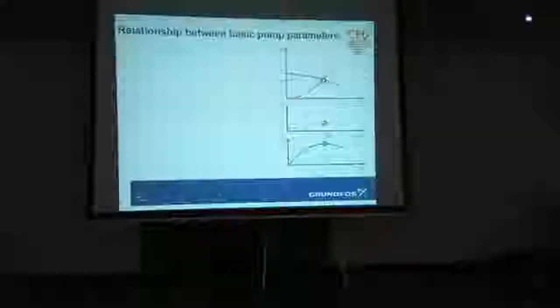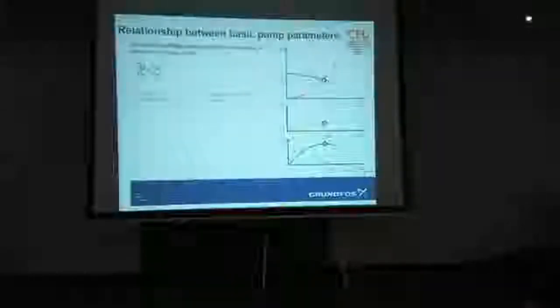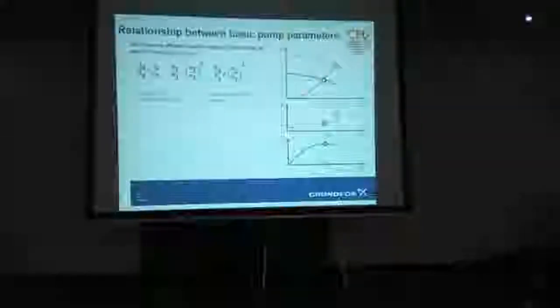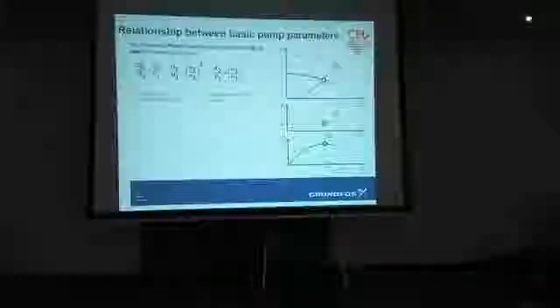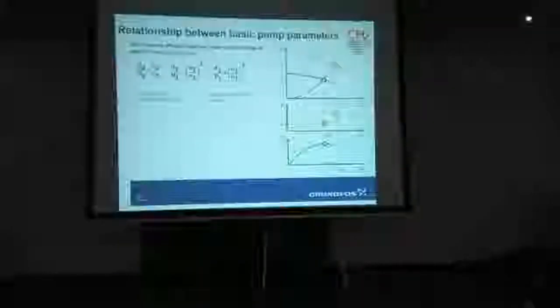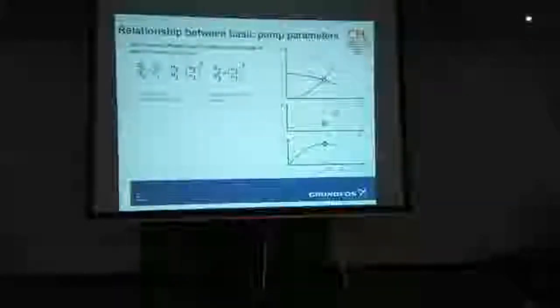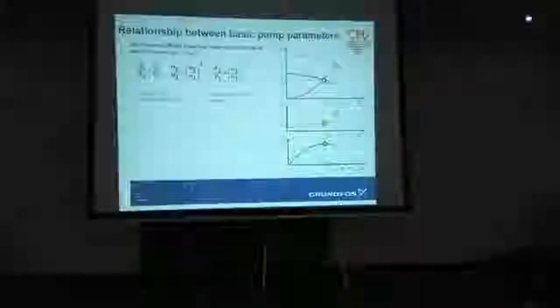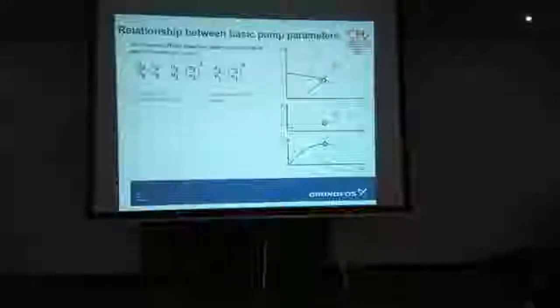Typical pump performance curve, that's the curve, the flow. There's a typical system characteristic curve. That's the power curve, and that's the efficiency curve. So at that point there, the best efficiency point, that's how it will look on the system. If we change certain parameters, like changing the speed, we reduce the power consumption, we reduce the speed, we reduce the flow. Or conversely, if that was using 1 kilowatt and we double the speed, that would be 8 times the power. Okay? Fans and pumps, which you all should be familiar with, I would imagine, somewhere on the line.